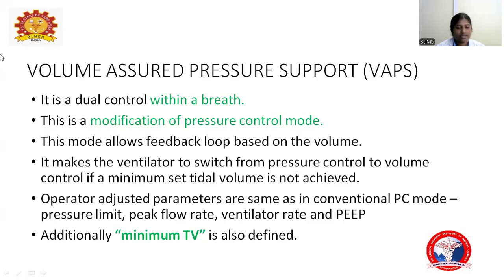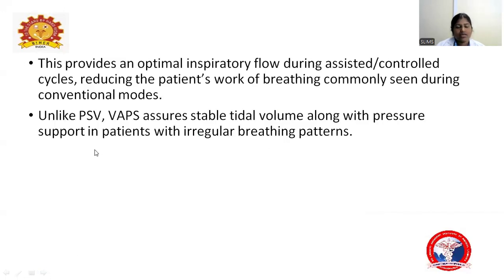The operator adjusted parameters are the same as in conventional pressure control mode. That is pressure limit, peak flow rate, and the ventilator rate and PEEP. Additionally, minimum tidal volume is also defined in this mode. So this provides an optimal inspiratory flow during assisted or controlled cycles, reducing the patient's work of breathing commonly seen in conventional modes. Unlike pressure support, this volume assured pressure support assures stable tidal volume along with the pressure, supporting the patient with irregular breathing patterns.